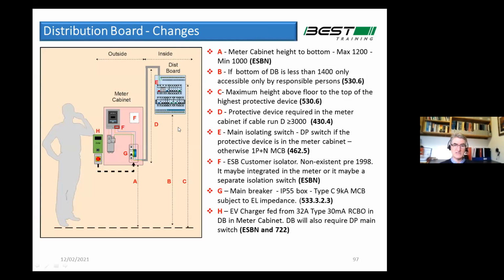That just doesn't apply to consumer units. It applies to other switchgear. Meter cabinets: some of the things that are going to happen, if the distance from the meter cabinet to the consumer unit exceeds 3 meters, you should be putting a breaker back here. You should have a circuit breaker here protecting this cable. And if you do put the circuit breaker here, then this becomes a double pole switch in your consumer unit. A lot of people are not following that and not fully realizing that is the requirement.